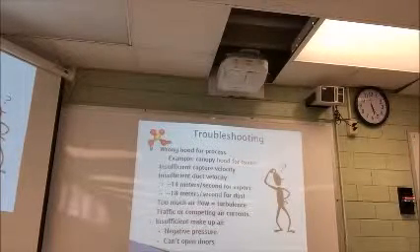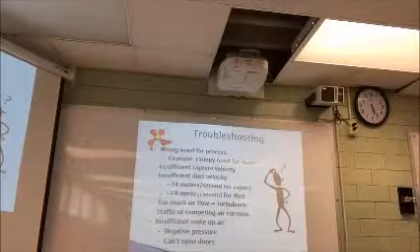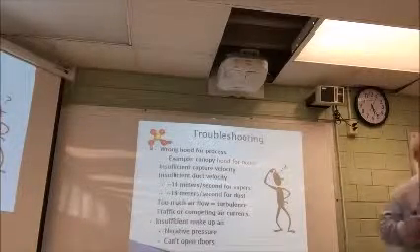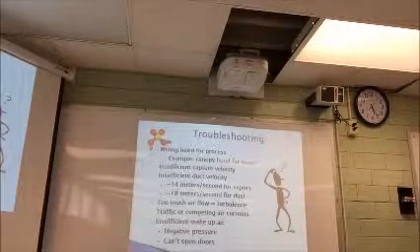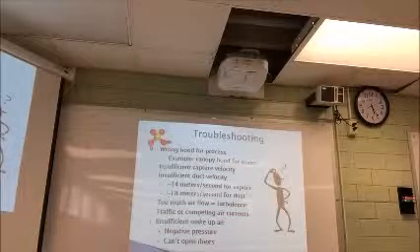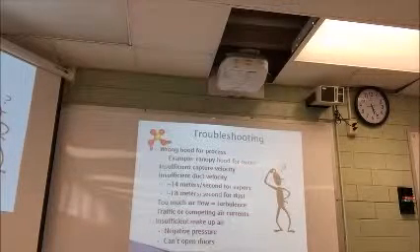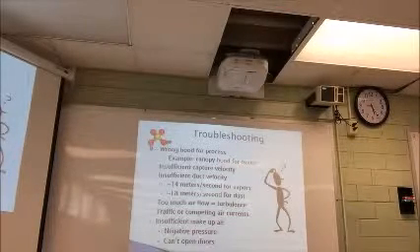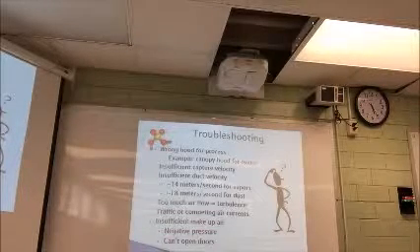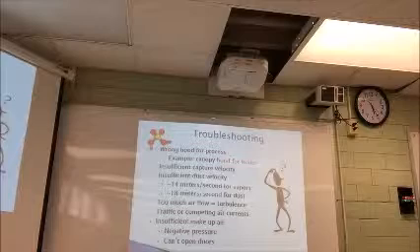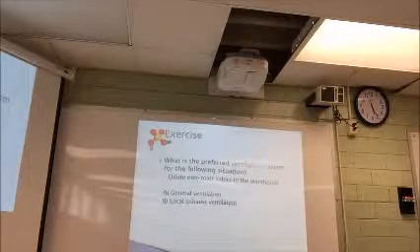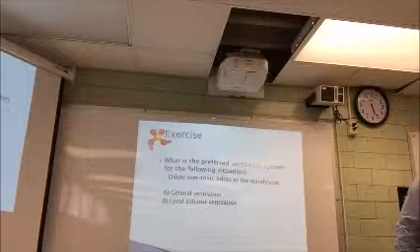Insufficient makeup. I installed for a combustible dust. It was a sugar plant. It was designed. We told them how much makeup we knew it would take. They said, we can't afford that extra makeup volume, we're going to cut it out. What do you guys think happened when it started working? It didn't remove the combustible dust. So guess what they did? Go back again, reinstall it. So they had to get the makeup volume. So just common errors.